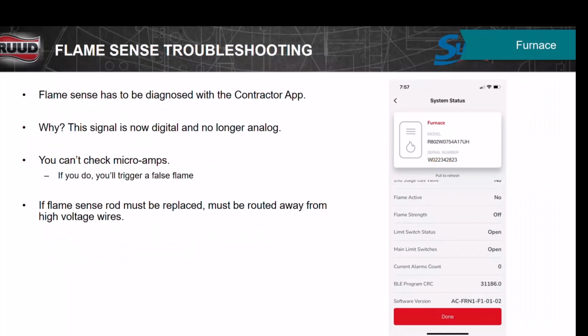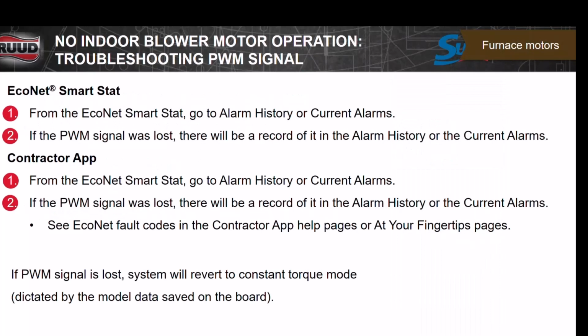The flame sense has to be diagnosed through the contractor app like we talked about a while ago. You go through here and you see the strength of the flame sensor. If the unit is off, it'll say off. There's a high, normal, and low. You can't check microamp. If you do have a flame sense problem, you can clean it with some steel wool or something. Don't put sandpaper on it. If that doesn't fix it, then you want to replace it. You can see all the alarm histories, current alarms in the EcoStat or on the app.